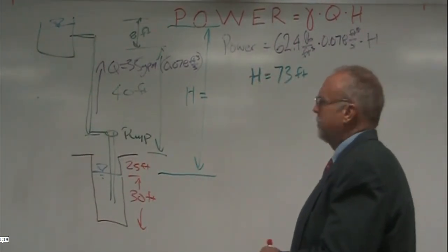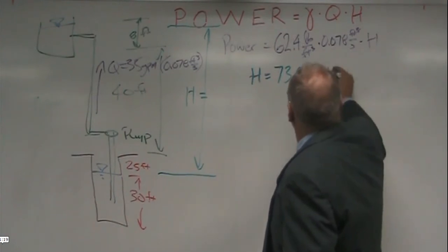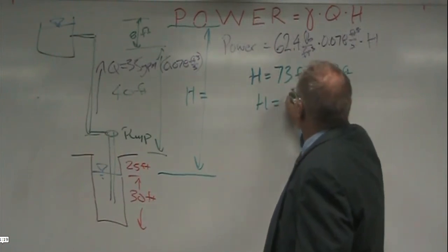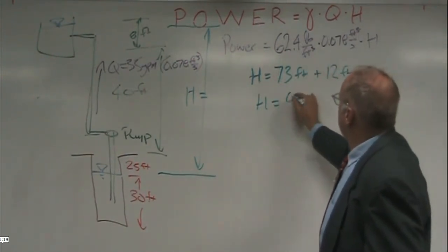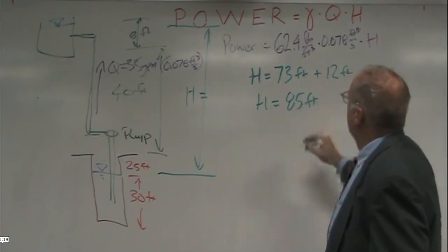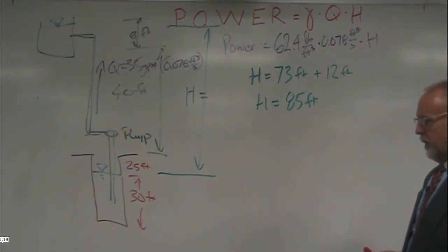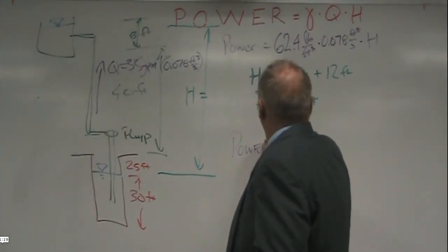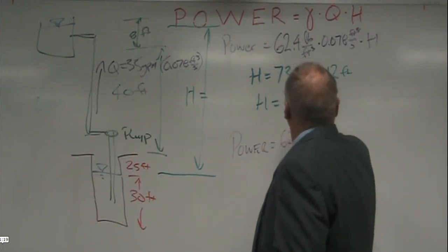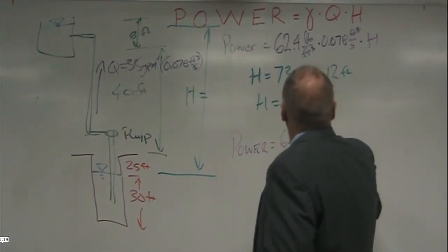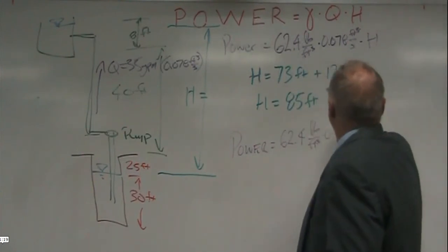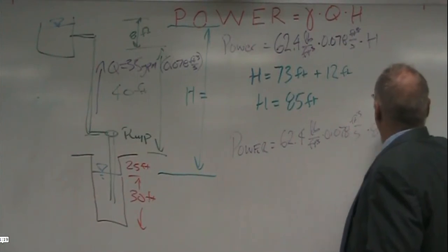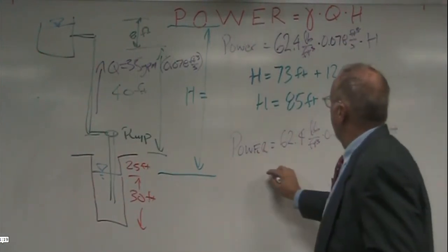So the head loss in this pipe system is 73 feet plus 12 feet. The total head we have to raise is 85 feet. All right, now let's plug that into our equation. The power equals 62.4 pounds per cubic foot times 0.078 cubic feet per second times 85 feet.